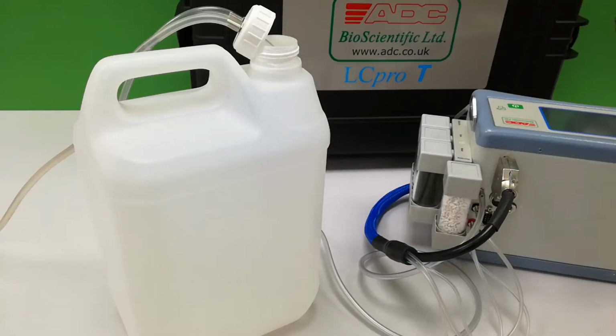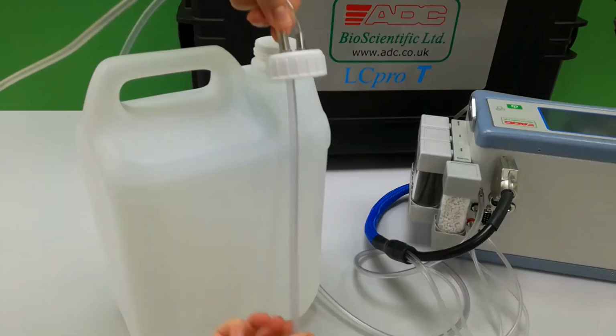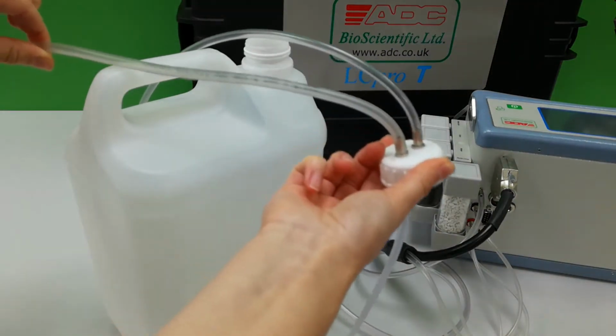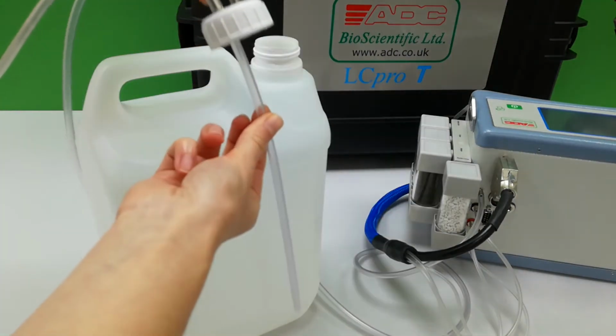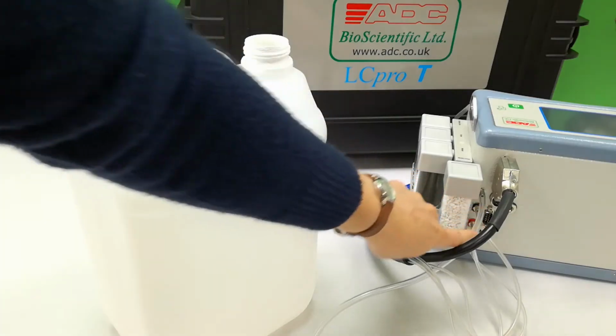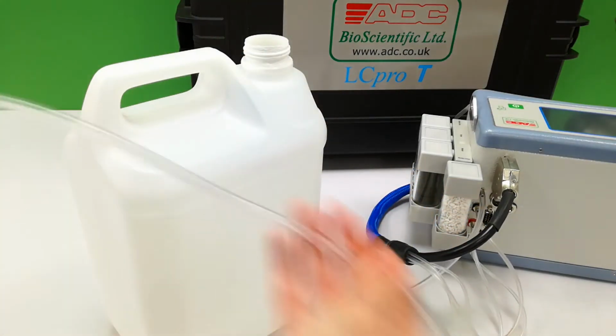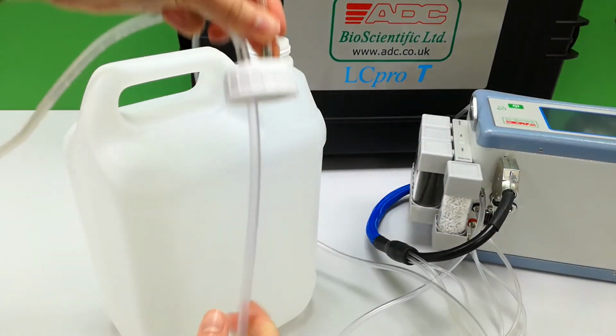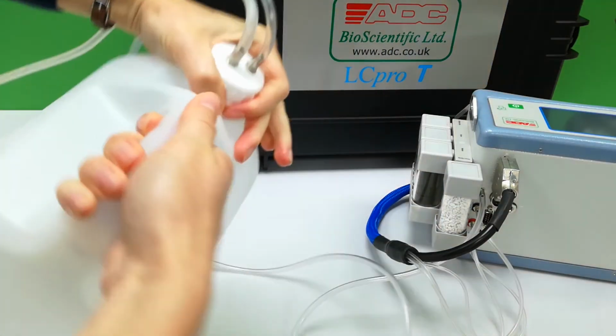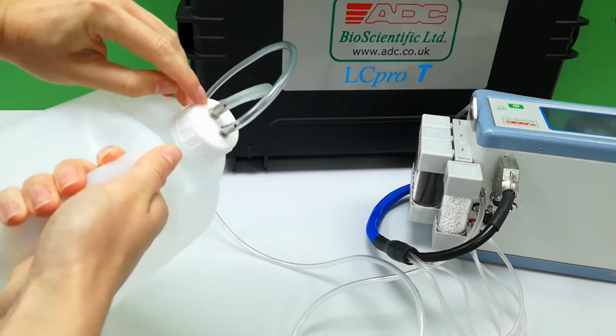For working indoors or in dense canopy, make a buffer volume between a source of outside stable air and LCpro T. If possible, source a clean 5-litre plastic container with a screw-top lid. One entry carries air to the tubing, which can be hung out of the window. This entry should have a second length of tubing hanging down inside the container. The air out entry is connected by another length of tubing to the LCpro T console.